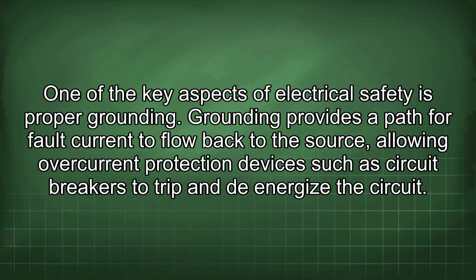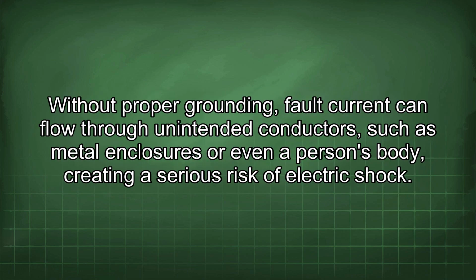One of the key aspects of electrical safety is proper grounding. Grounding provides a path for fault current to flow back to the source, allowing overcurrent protection devices such as circuit breakers to trip and de-energize the circuit. Without proper grounding, fault current can flow through unintended conductors, such as metal enclosures or even a person's body, creating a serious risk of electric shock.